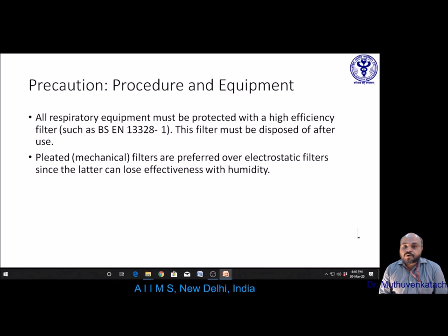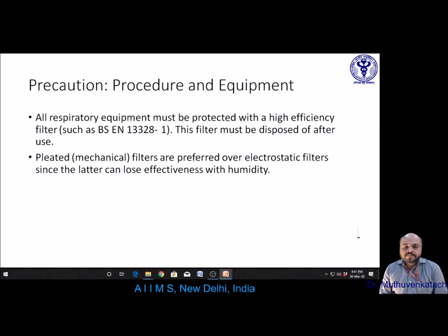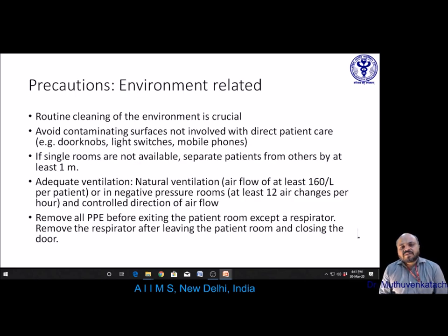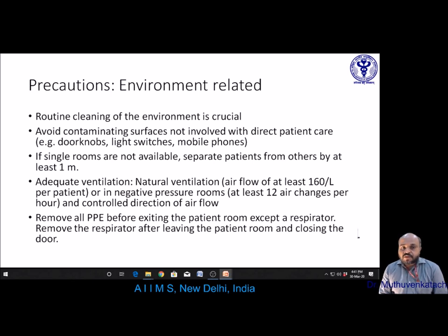All respiratory equipment must be protected with a high-efficiency filter — pleated mechanical filters are preferred over electrostatic filters as electrostatic filters lose effectiveness with humidity — and must be disposed of after use. Regarding environmental precautions in the ICU or isolation room, routine cleaning of the environment is crucial. Avoid contaminating surfaces not involved with direct patient care such as door knobs, light switches, and mobile phones. If single rooms are not available, ensure patients are separated by at least one meter apart. Provide adequate ventilation with natural air flow of at least 160 liters per patient or negative pressure rooms with at least 12 air exchanges per hour.